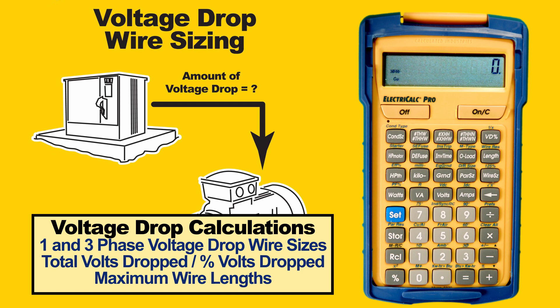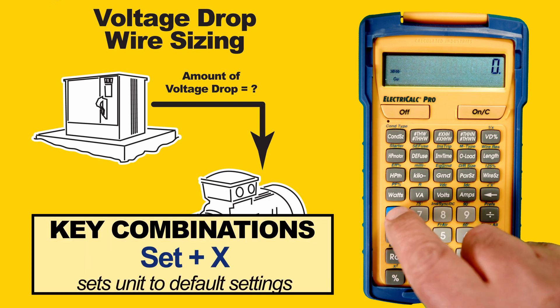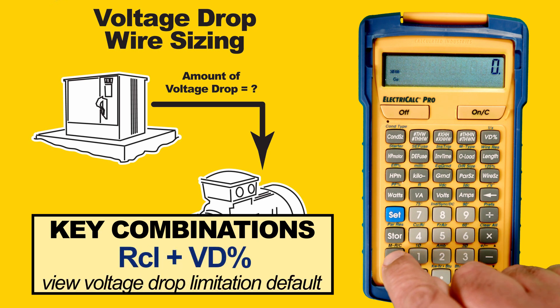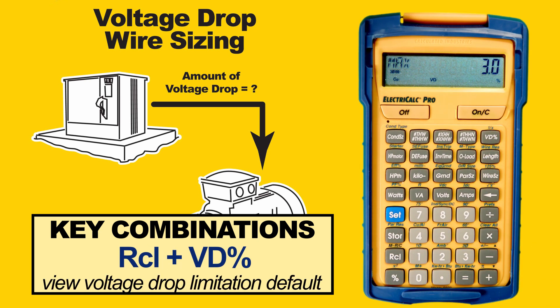We'll start by doing an all-clear. This is done by pressing the Set button, then the Times button, which clears everything to its default settings. We verify what code year we are working in — we are set to 2020, which is what we want. Press Clear. It will also set the voltage drop limitation back to its 3% default. To view this, press Recall, then VD%, which shows 3% max percent. You can change this easily, but we'll start off using that value.